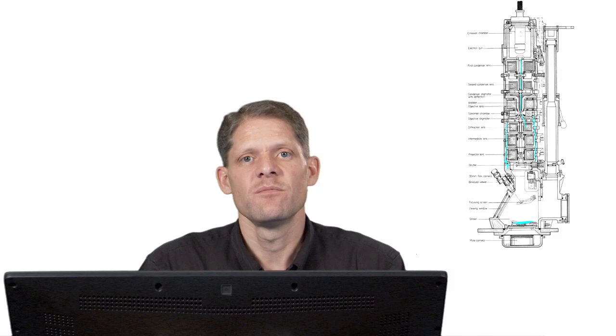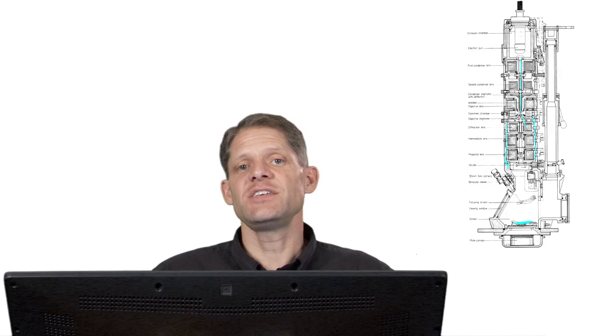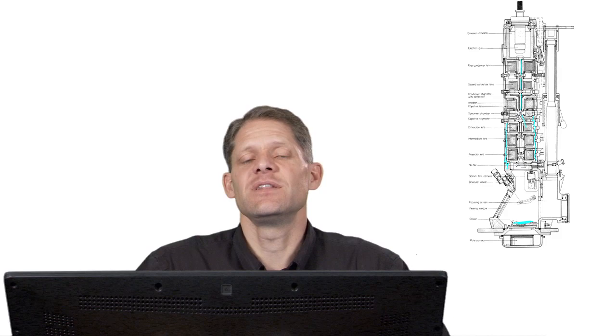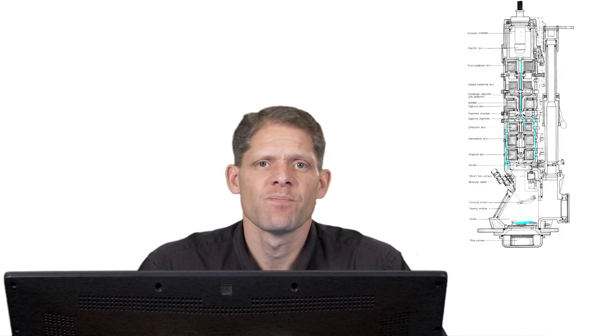We mentioned earlier that there is an asphyxiation hazard associated with electron microscopes. A high-tension tank is insulated with a gas, sulfur hexafluoride, that is both odorless and colorless. So if there's a leak in the compressed sulfur hexafluoride tank, it can fill the room and displace the oxygen and cause an asphyxiation hazard.